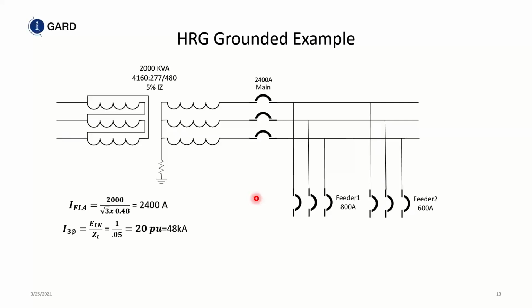Same transformer we had before. Full load current of 2400 amps, 48 kA bolted fault current, even though there's an impedance over here. So that resistor on this system, we limit that fault current to 5 amps, is a 55 ohm resistor. 277 divided by 5 amps equals 55 ohms. A 55 ohm resistor protects everything on the secondary of that transformer, right down to the very last 1 horsepower motor. Everything on the entire secondary is credited with an arc flash mitigation technique because of this resistor, which is smaller than a bread box.